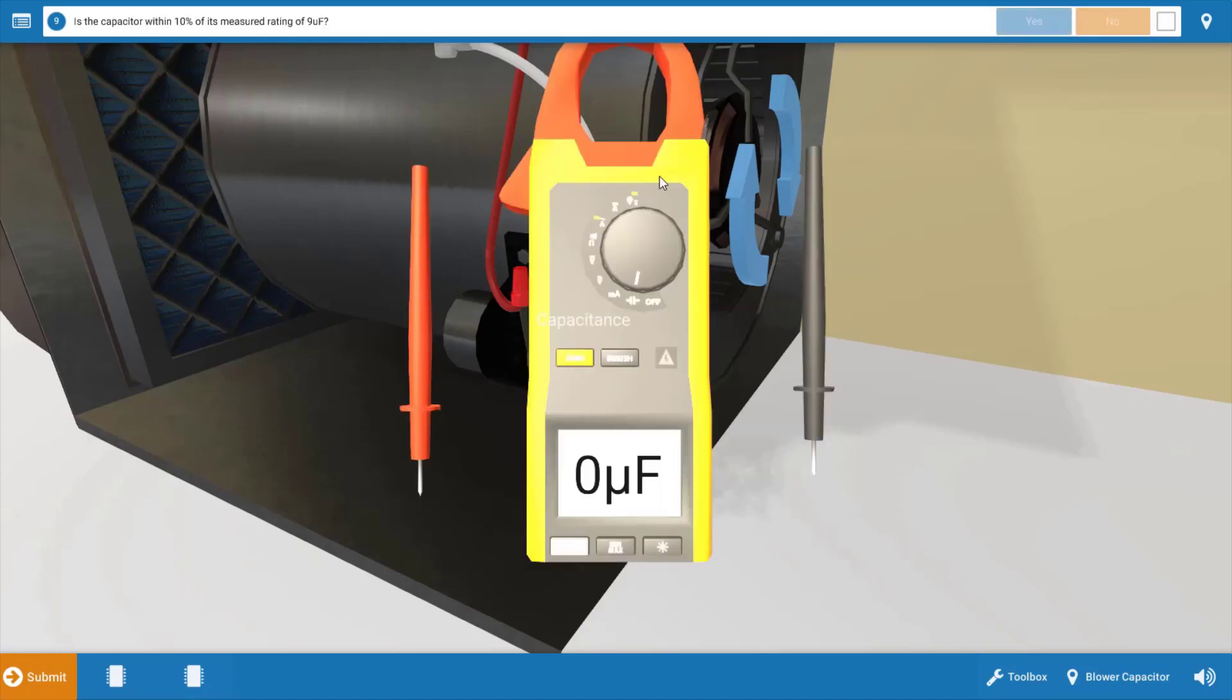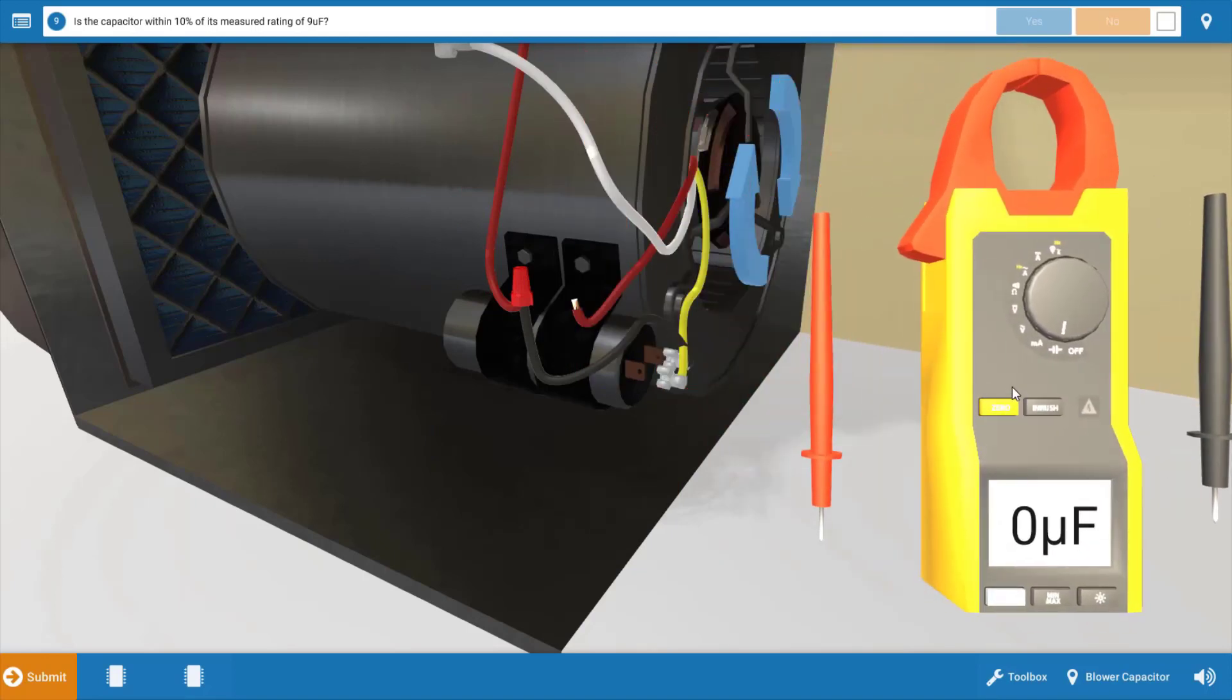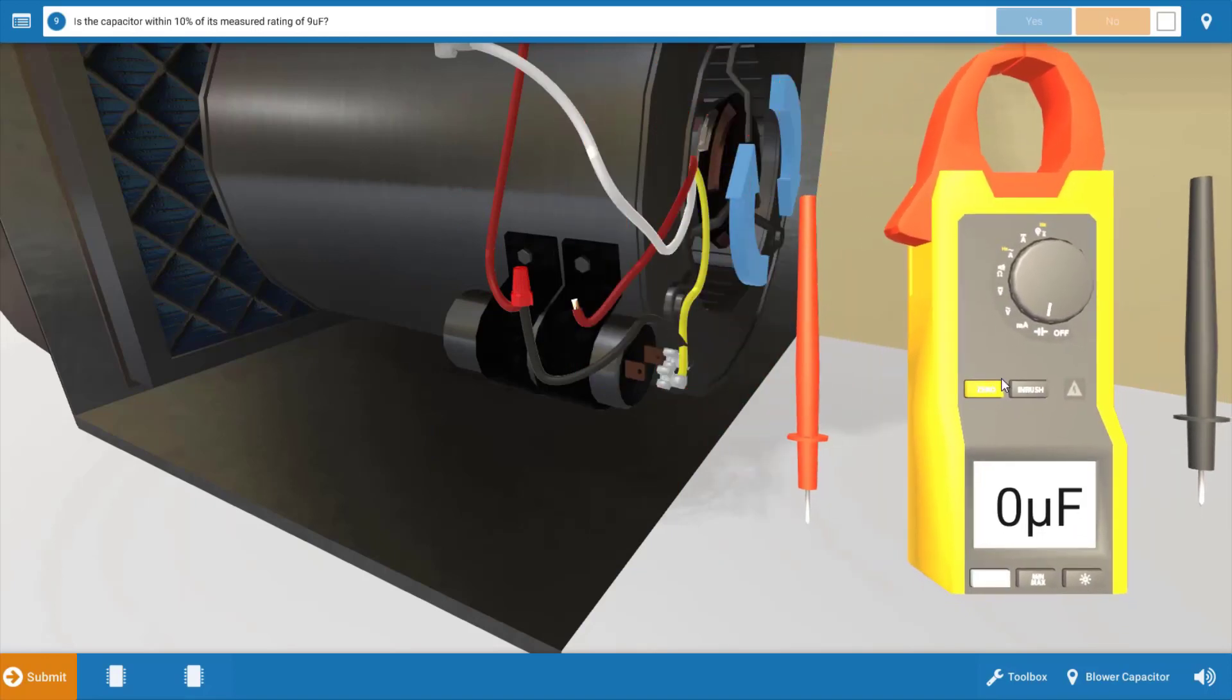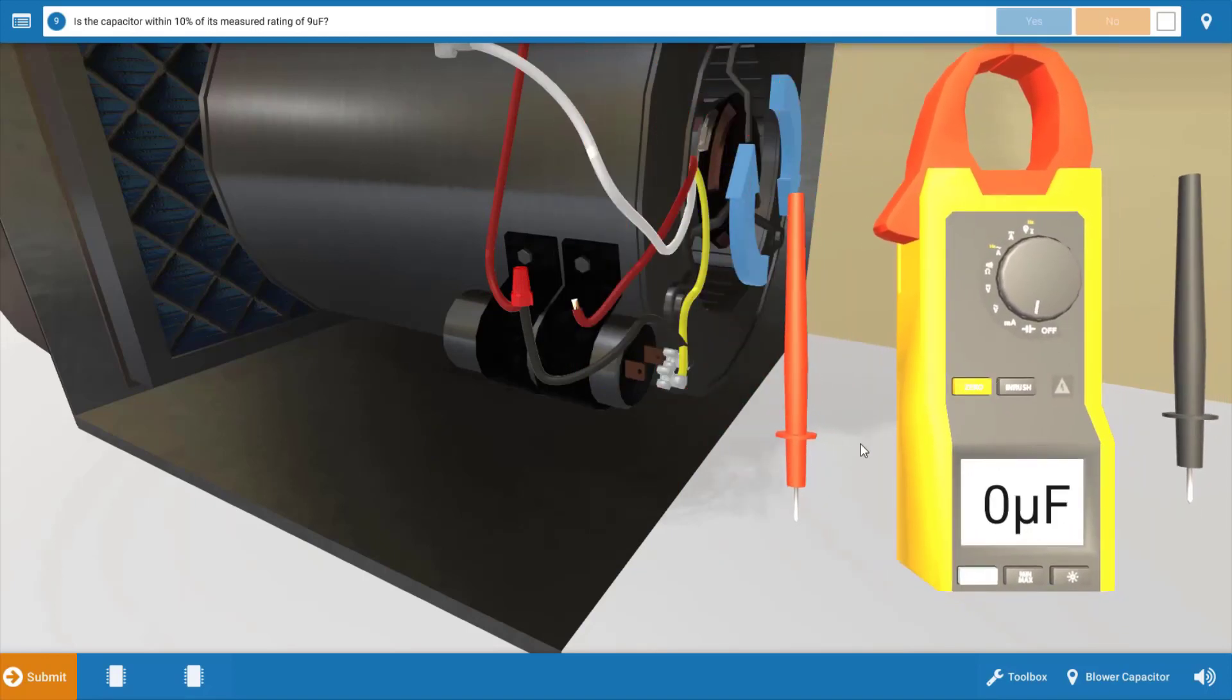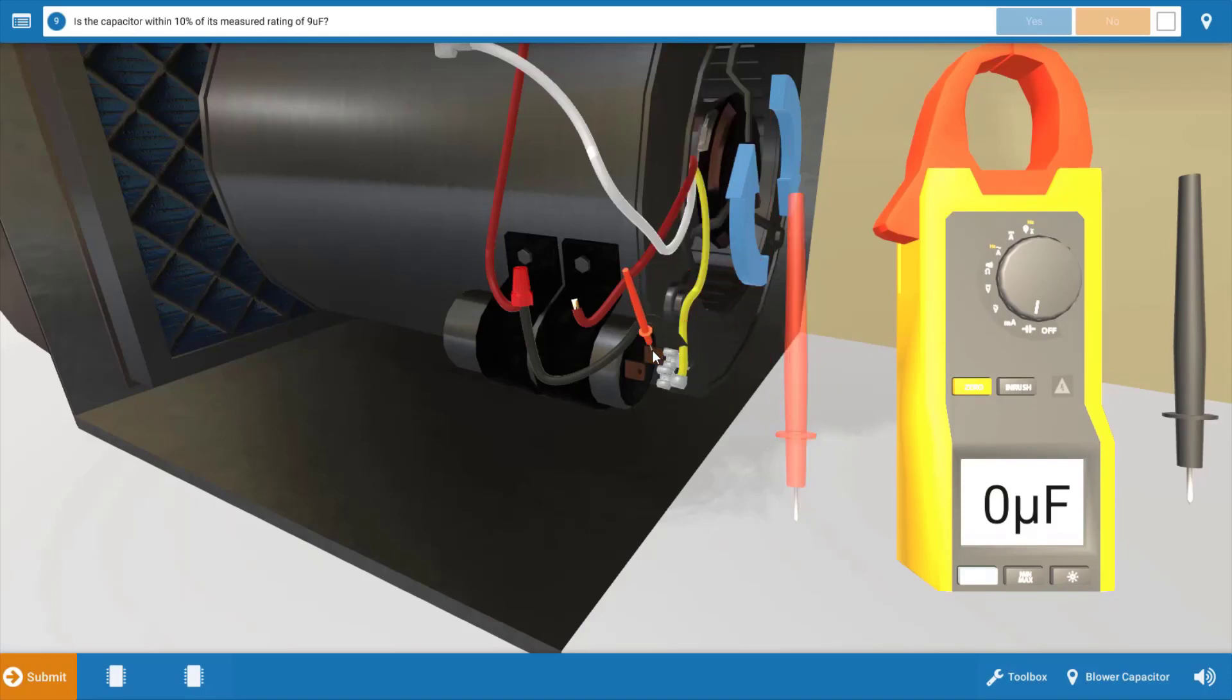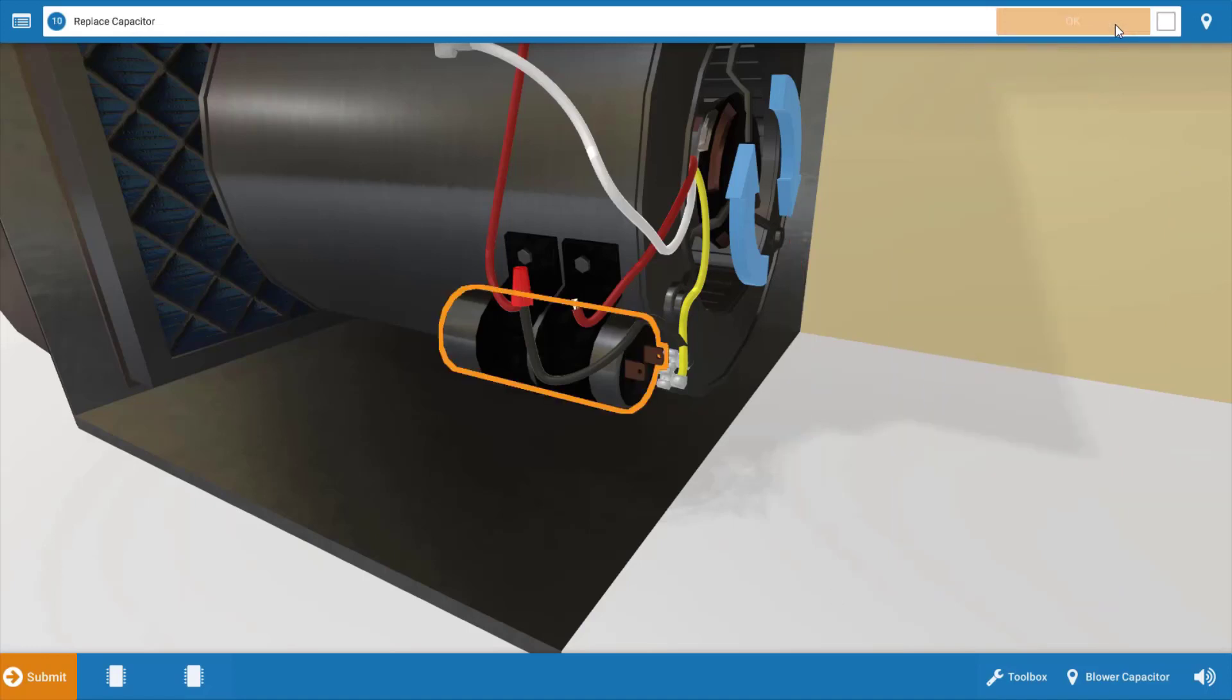Our next step is to measure the capacitance or microfarad value of the capacitor. This particular microfarad rating is nine microfarads. We're going to place our meter leads at the capacitor terminals and see if we get our nine microfarads plus or minus 10 percent of that value. We've got zero microfarads. This indicates that we have a faulty run capacitor here. And this is what's not allowing the blower motor to operate. So we've solved the problem. Our next step is to replace the capacitor.